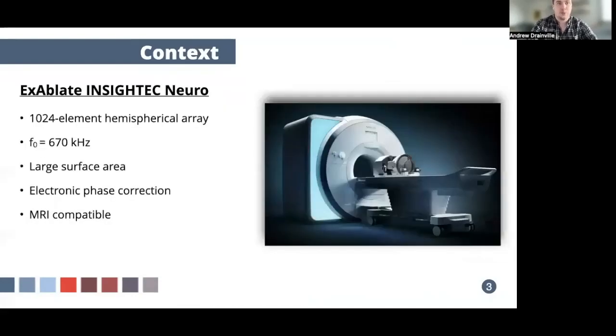To address these challenges, one of the most important systems for transcranial ultrasound is the Exablate Insightec Neurosystem. It's an ultrasound transducer composed of 1,024 elements arranged in a hemisphere operating at 670 kHz. The large surface allows for focusing across the surface of the head with phase correction for each of its elements to account for the presence of the skull.